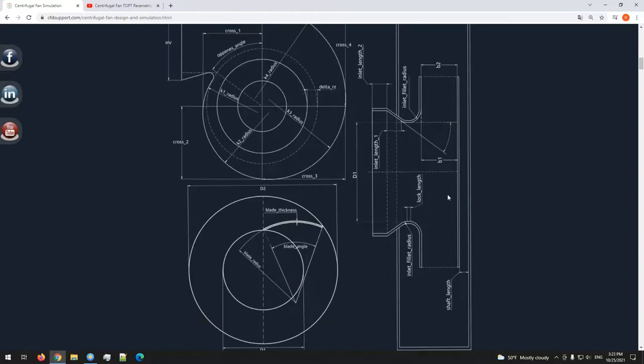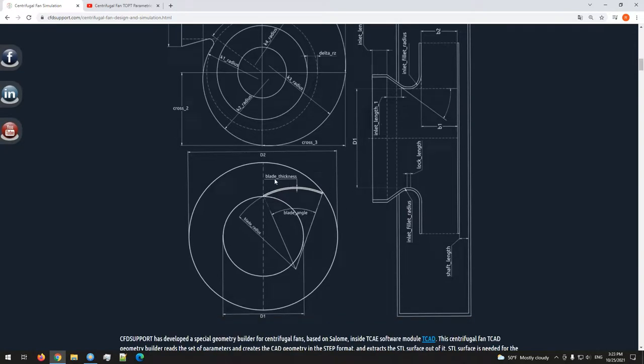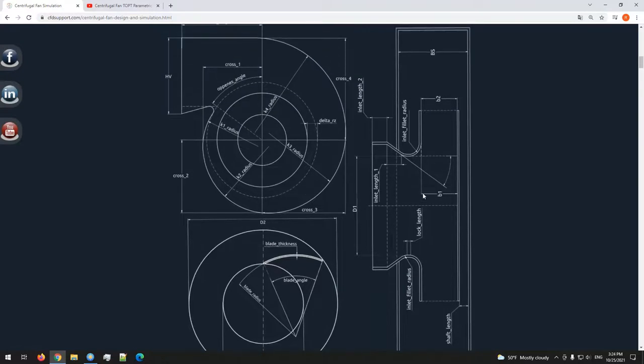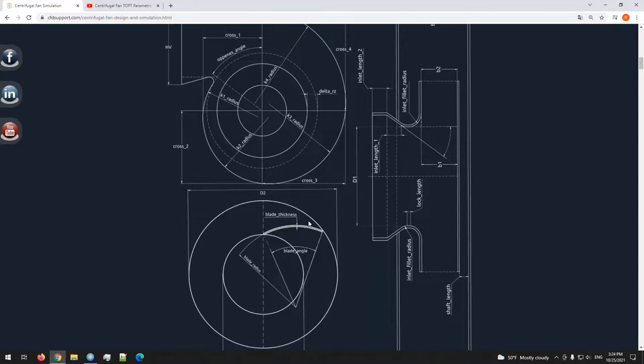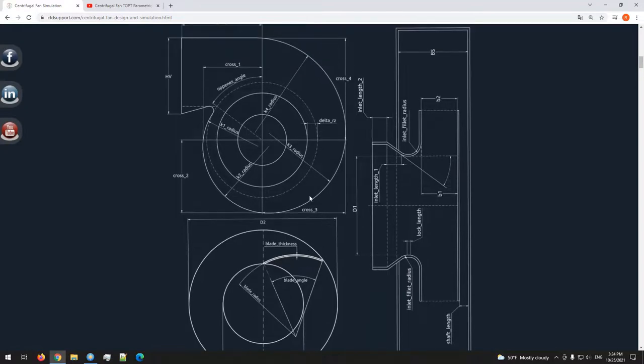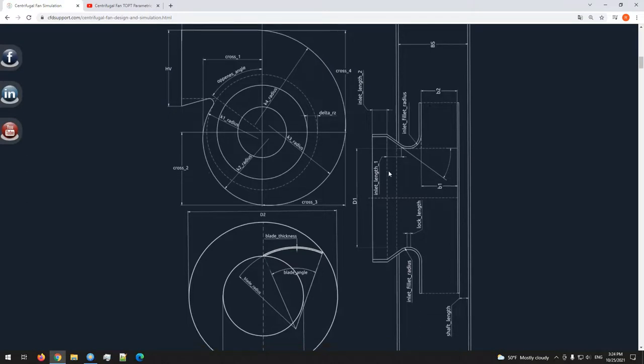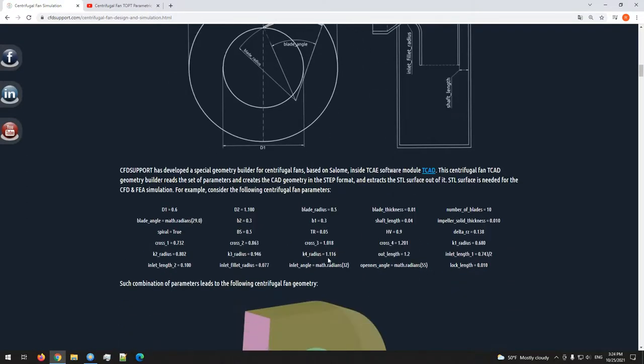or to improve the efficiency. So basically what we will optimize is 5 parameters. One is the number of blades, which is pretty easy. Then there is the blade thickness, the blade radius, the blade angle, so how long the blade is, and the last one is the width of the impeller itself. These B1 and B2 parameters are set to the same value. So this is some kind of middle-size fan.